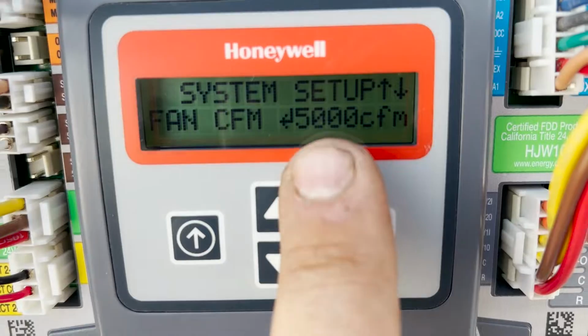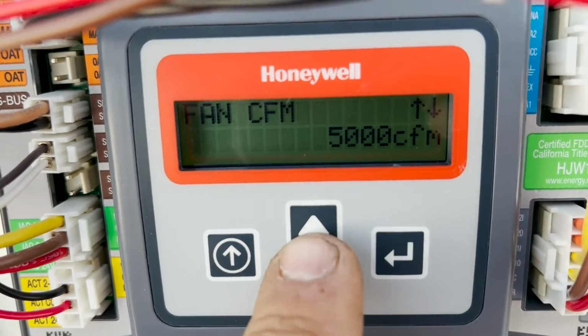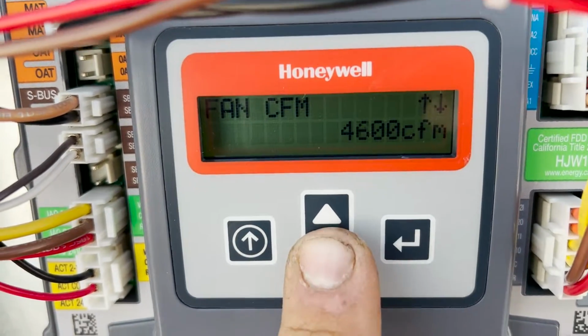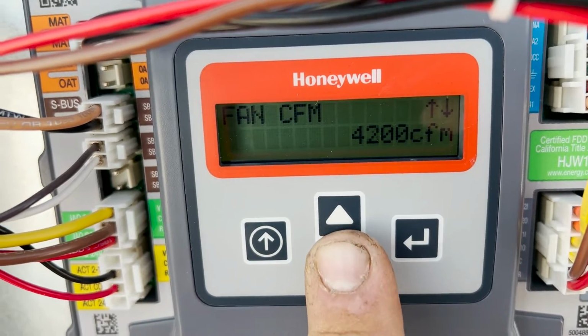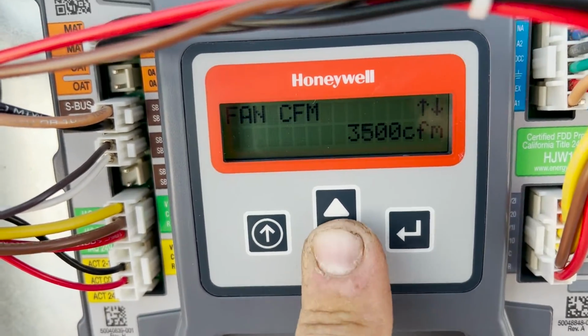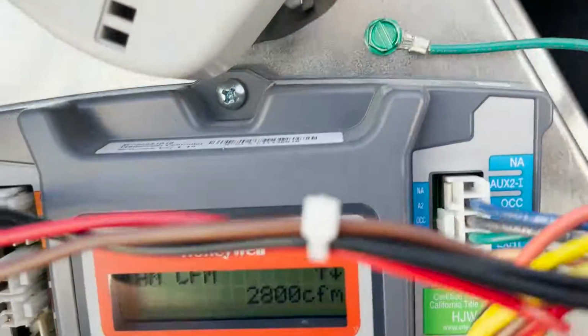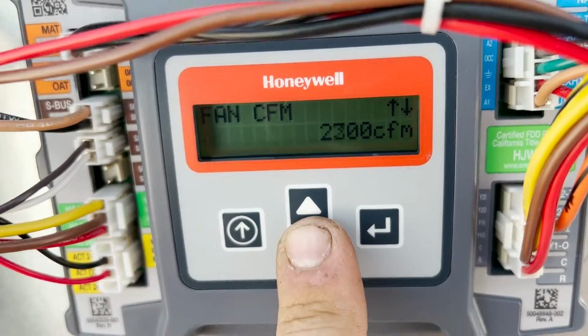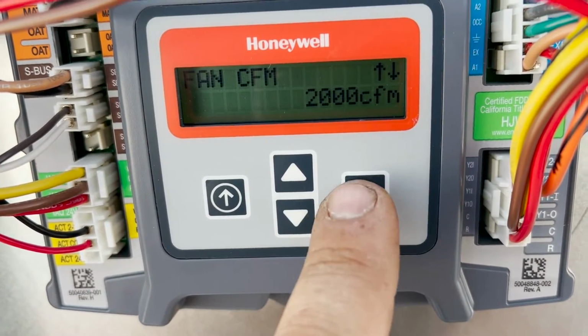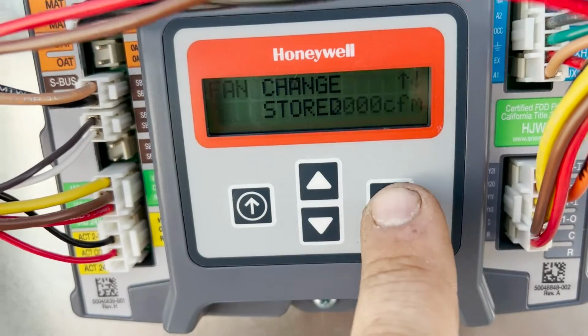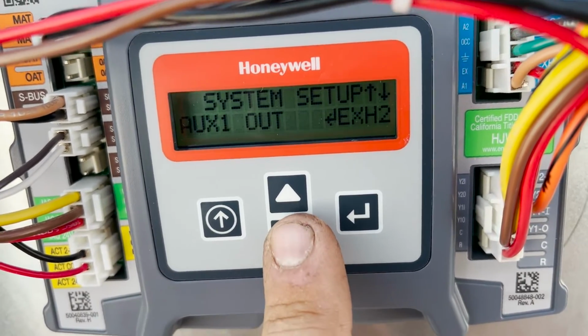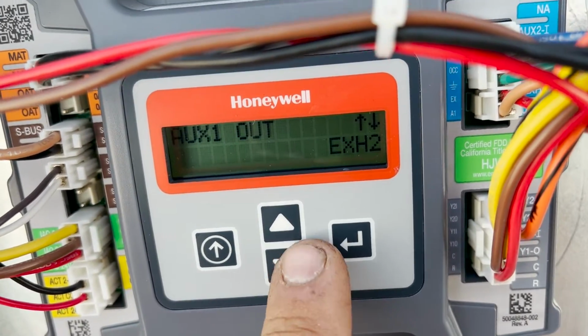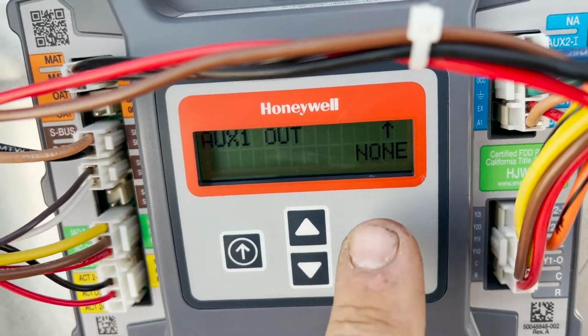Airflow 5,000, not correct. This is a 5-ton unit, so our nominal CFM is 2,000. And this matters because it's gonna try to open this damper according to how much air it thinks is going past it. There is no power exhaust or ERV.